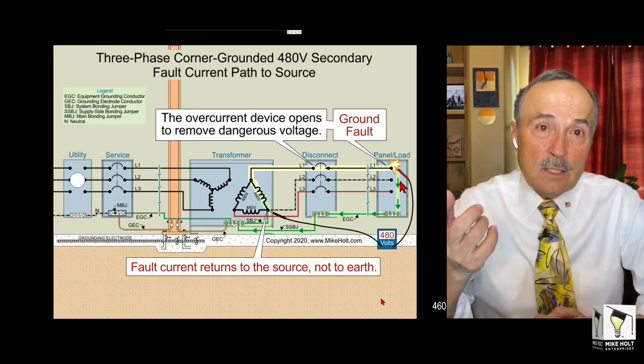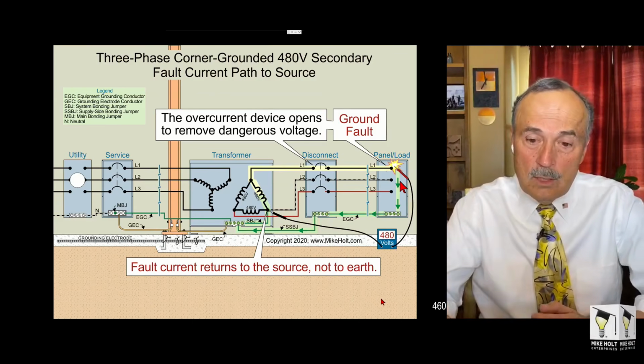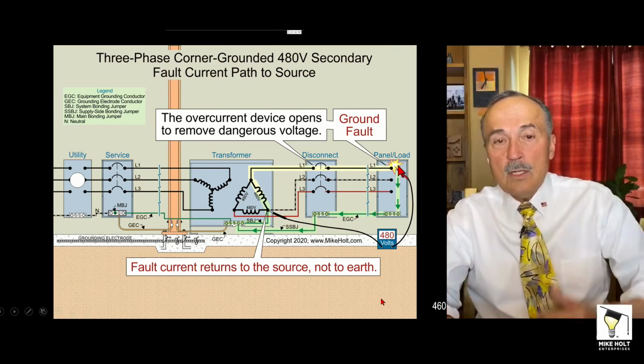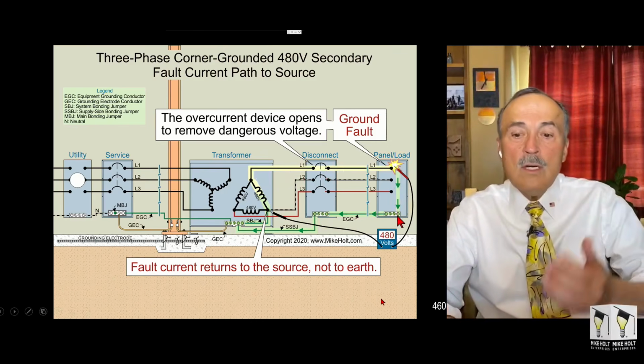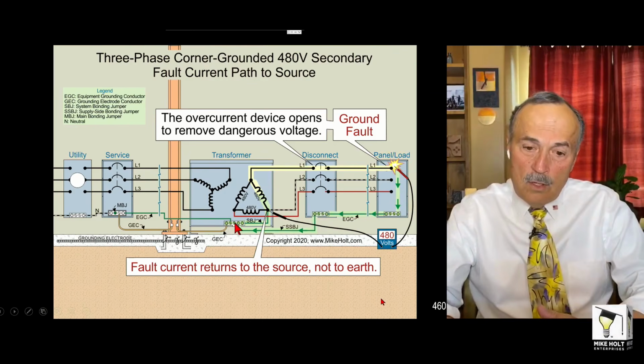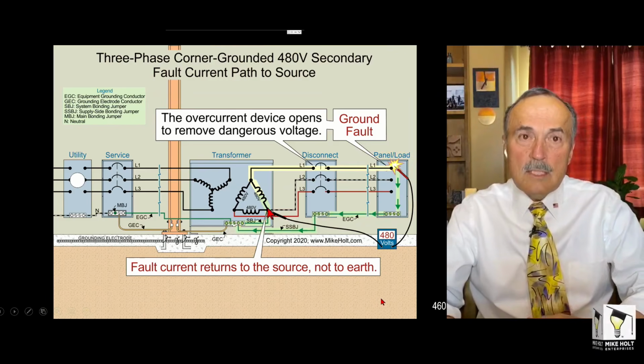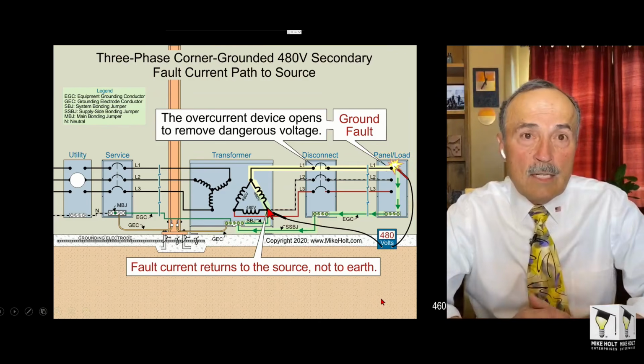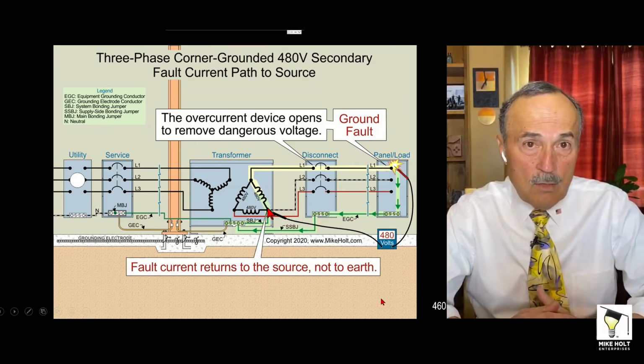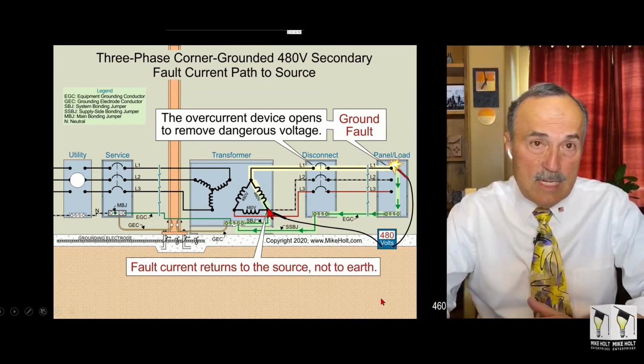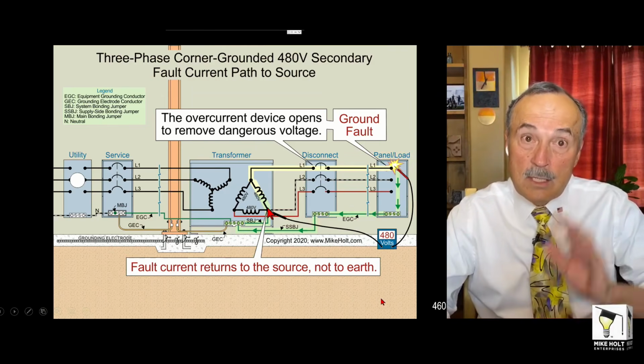But if another phase goes ground faulted, well, then the fault current leaves the source, goes to the overcurrent device, gets to the enclosure ground fault, travels on the effective ground fault current path, and gets back over to the system, and then opens the protection device. The electrons are never going to ground, guys. Don't be driving ground rods to try to make it safe, because that doesn't make a difference. Another day we'll talk about that.